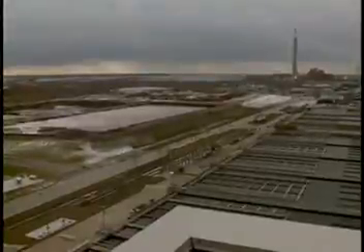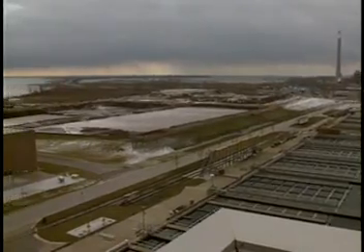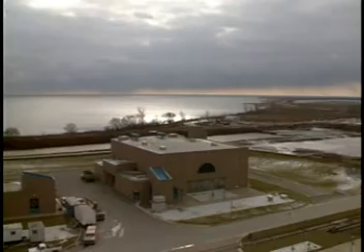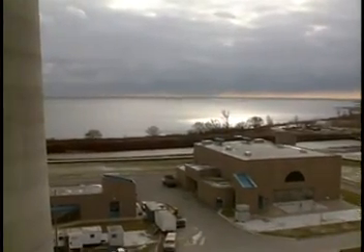Starting to look like water now. That's why they have railings. The water in these pools is flowing into Lake Ontario. As it does, chlorine is injected to zap any remaining pathogenic microorganisms — that's what we used to call germs. The disinfected outflow is returned to the lake underwater about 1,000 meters offshore. That dark spot is turbulence, not dirty water.